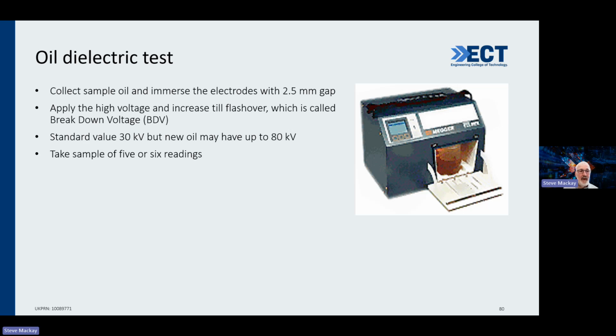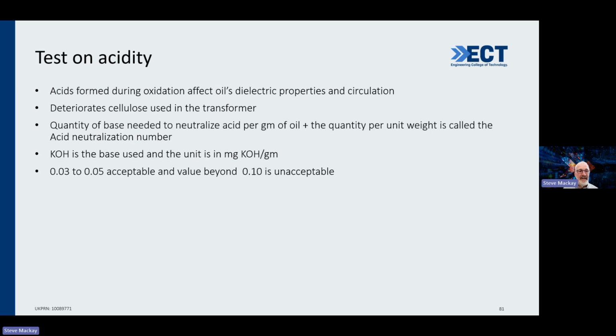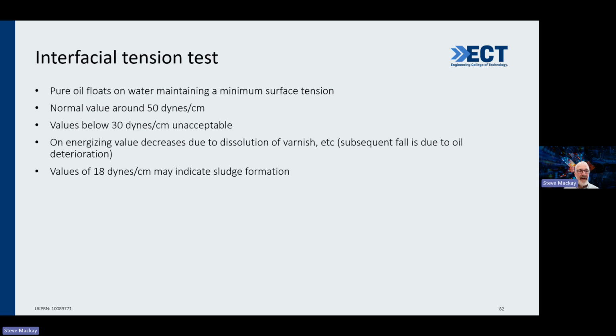And then here's some oil dielectric tests. I remember many happy hours doing oil dielectric tests and obviously looking at the breakdown voltage. So there's a whole thing there. And obviously the other thing is acidity tests. It's always fascinating that you can have acidity in oil. That's obviously pretty critical. And obviously KOH, potassium hydroxide, is very important to use there. Interfacial tension test. You have a minimum surface tension, and you need to look for interfacial tests.